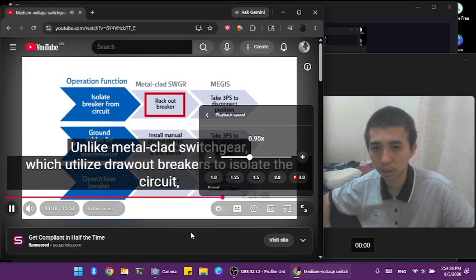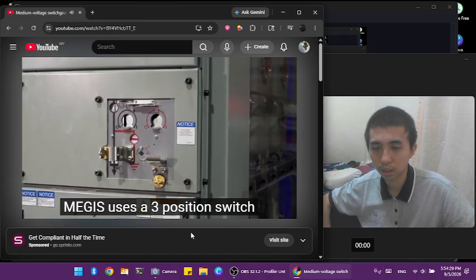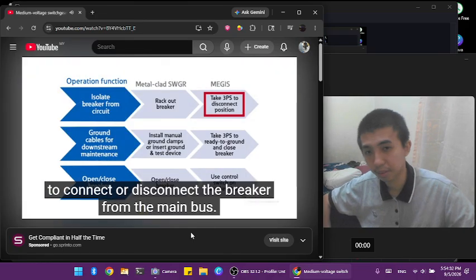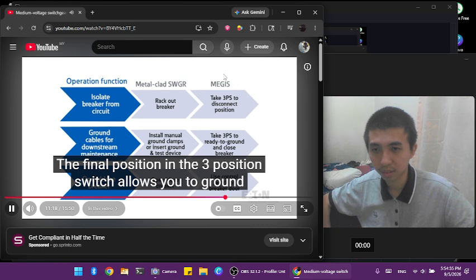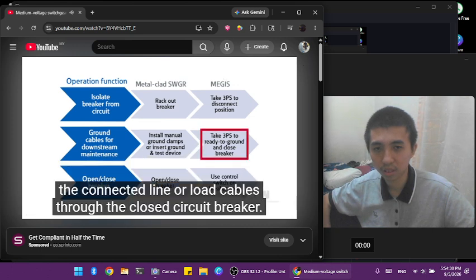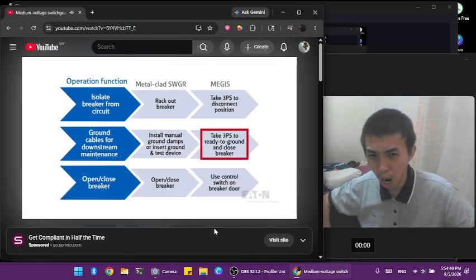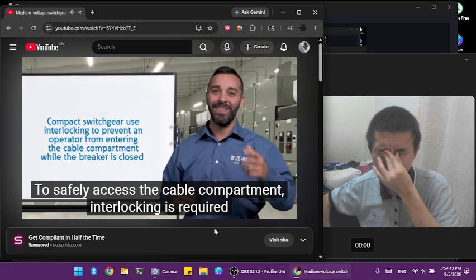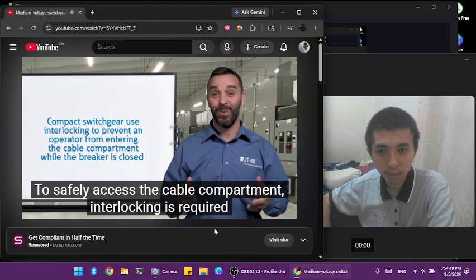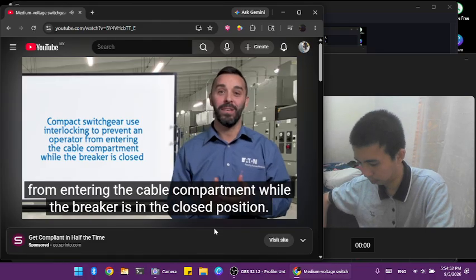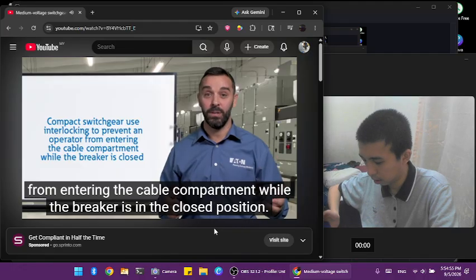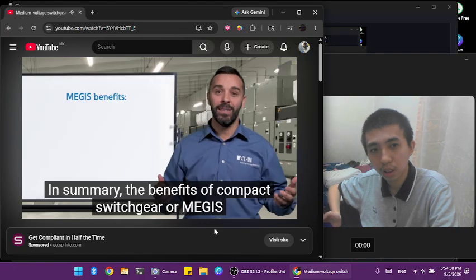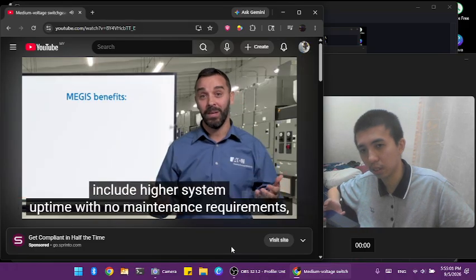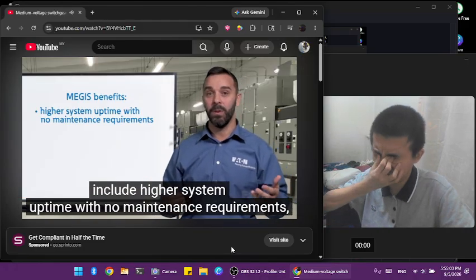Unlike metal-clad switchgear, which utilizes draw-out breakers to isolate the circuit, MEGIS uses a 3-position switch to connect or disconnect the breaker from the main bus. The final position in the 3-position switch allows you to ground the connected line or load cables through the closed circuit breaker. To safely access the cable compartment, interlocking is required with the main breaker to prevent an operator from entering the cable compartment while the breaker is in the closed position.